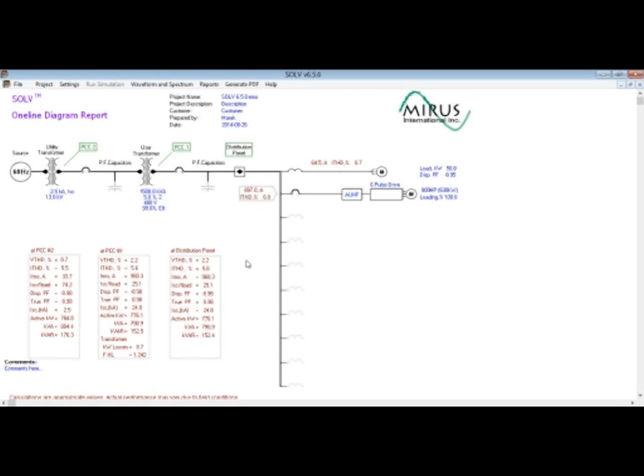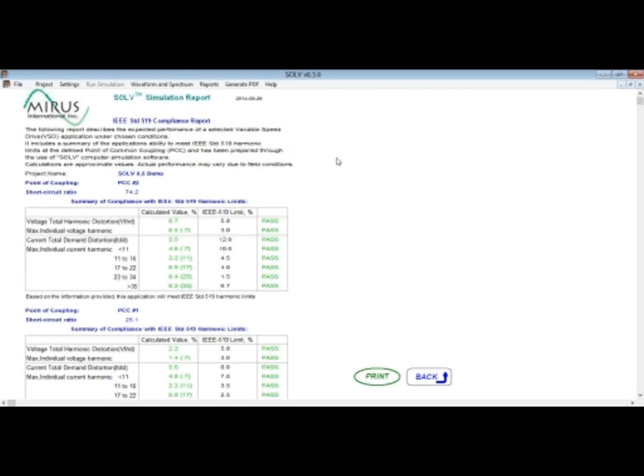So after calculation is done, we can see current distortion at the VFD load branch has dropped dramatically to 6%. Also the voltage distortion on the PCCs upstream has been reduced as well. For example, PCC1 voltage THD is 2.2% and current THD is 5.6%. Selecting reports and opening the compliance report page, we can see that now we meet the requirements for both PCCs for voltage and current distortion.